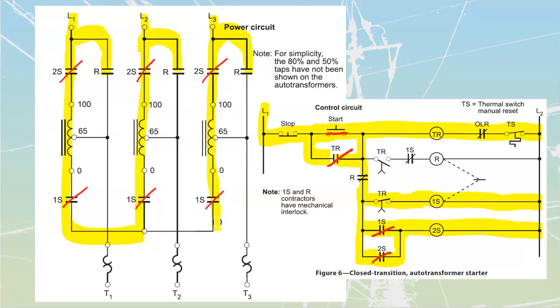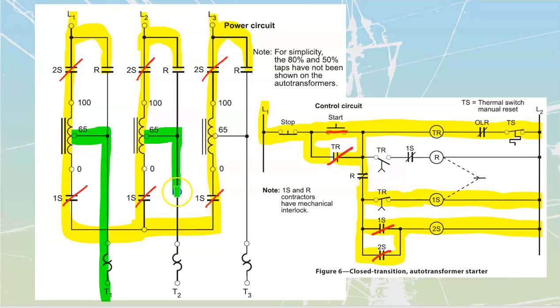So we see that the starting contactors over here provide power down to that Y point. And as soon as we provide that power down to the Y point, we can then tap off from here and feed out to my individual motor leads over here. So we're going to have power fed through to my motor itself. That is going to start up my motor right now. My motor is starting on my 65% tap at this point.